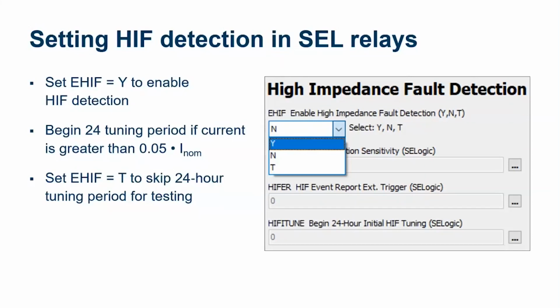And so once we establish that stable reference after the 24-hour period, we're going to arm the element and then go into what's called normal tuning, which allows it to adapt to changes in the loading and changes that it sees in that interharmonic energy, but it will adapt more slowly. So if, say, you just wanted to test the element, that's what we have this T setting for, this test. What that does is skip the 24-hour tuning period, and that's used for testing purposes only.